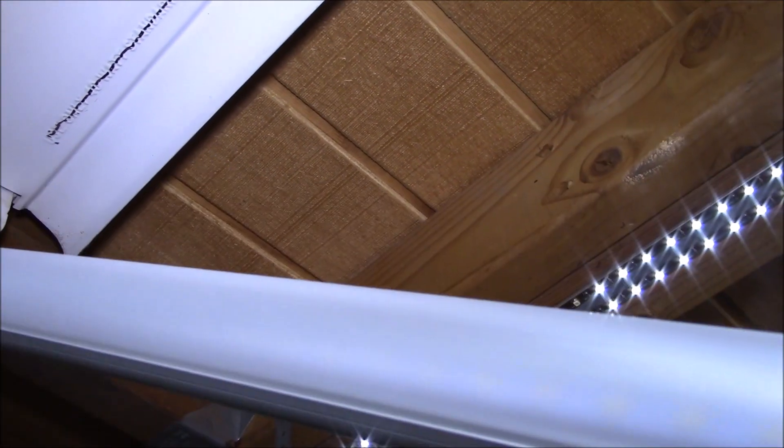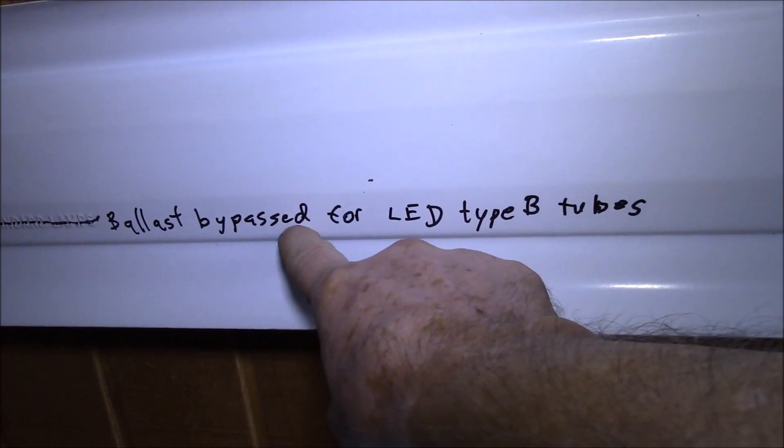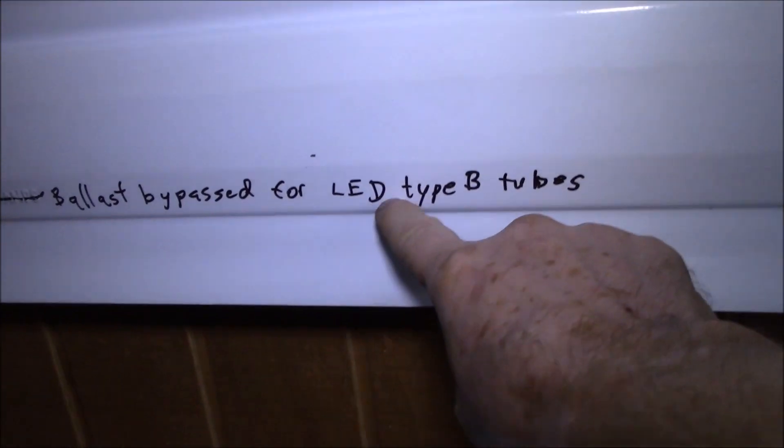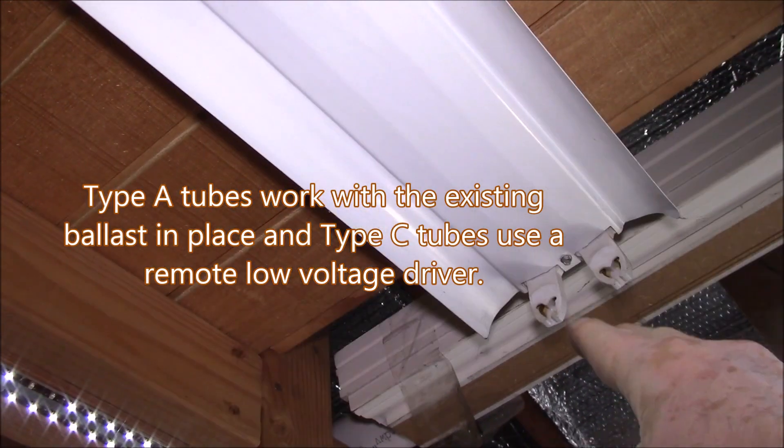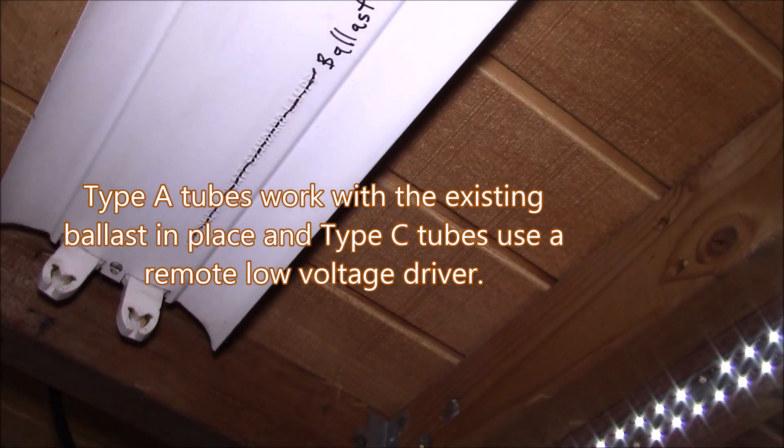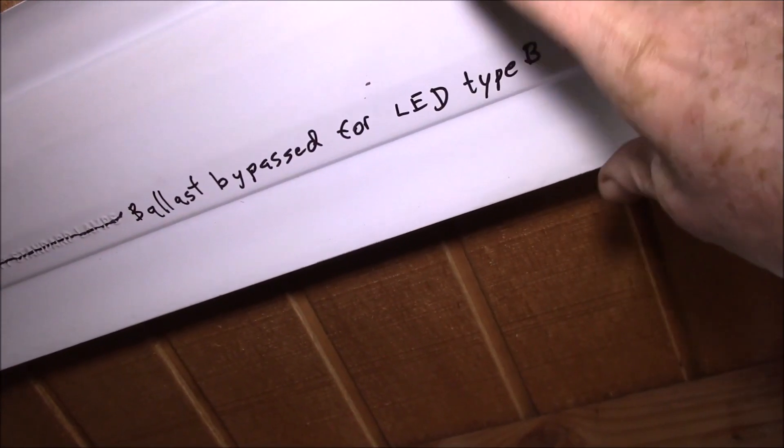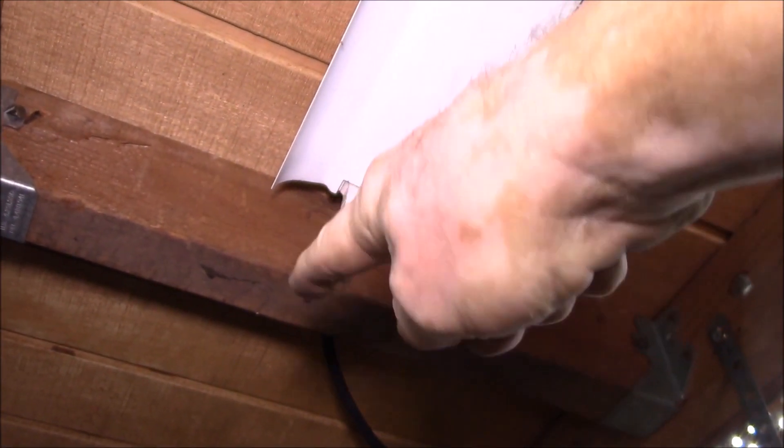I labeled these that the ballast has been bypassed for LED type B tubes. A type B tube has live at one end and then neutral at the other end. The reason I did these in place is I didn't want to take them down. The power wires are fed through the ceiling rafters there. It would probably double the amount of work to take these things down to work on them on the ground.